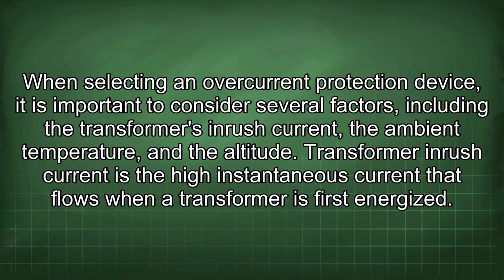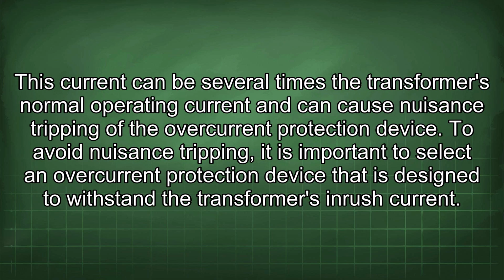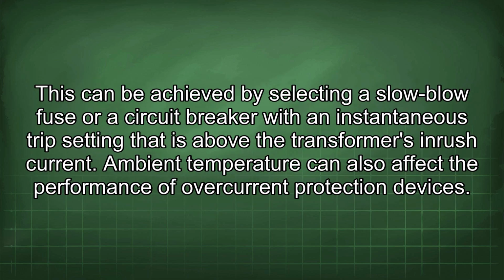Transformer inrush current is the high instantaneous current that flows when a transformer is first energized. This current can be several times the transformer's normal operating current and can cause nuisance tripping of the overcurrent protection device. To avoid nuisance tripping, it is important to select an overcurrent protection device that is designed to withstand the transformer's inrush current. This can be achieved by selecting a slow-blow fuse or a circuit breaker with an instantaneous trip setting that is above the transformer's inrush current.